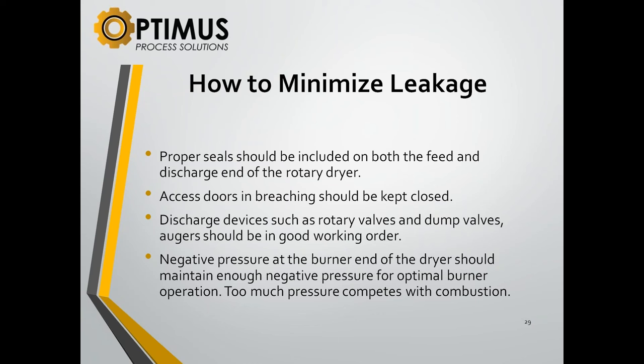Move this over. There we go. Okay. So minimize leakage. You do that with proper seals on both the feed and the discharge end of the dryer. You want access doors and breaching to be kept closed. On many of the dryers that we would build, we might have a tipper door where the dryer discharges into the discharge hood, and it's counterweighted so that no material is being discharged. It's closed.